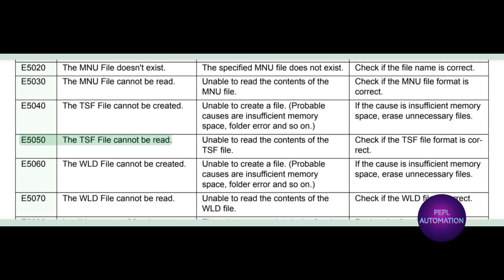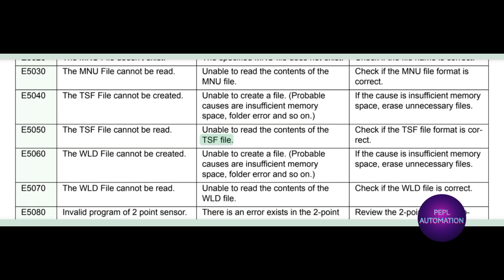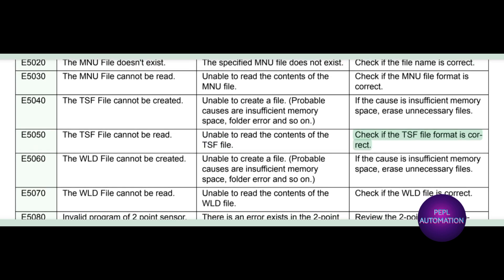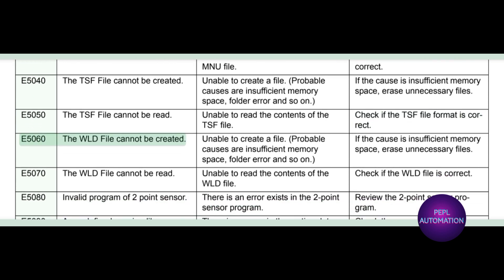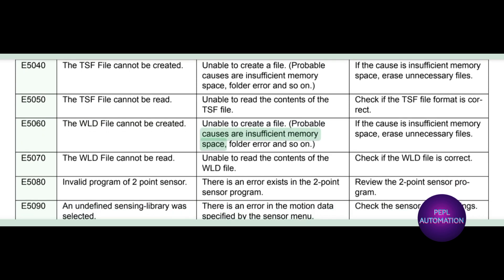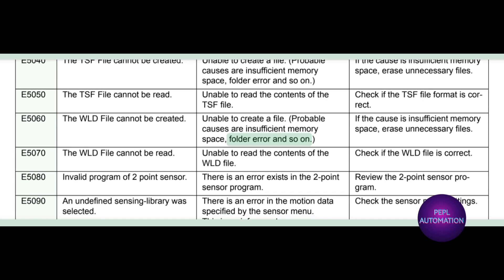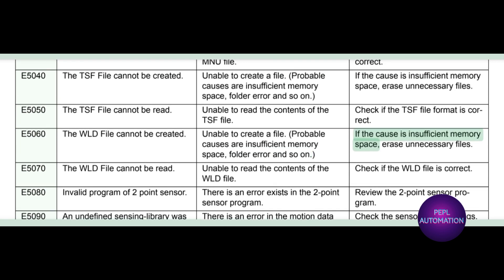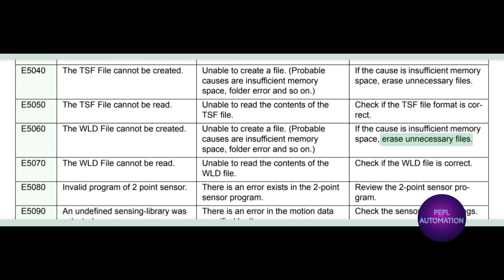E5050: the TSF file cannot be read. Unable to read the contents of the TSF file. Check if the TSF file format is correct. E5060: the WLD file cannot be created. Unable to create a file. Probable causes are insufficient memory space, folder error, and so on. If the cause is insufficient memory space, erase unnecessary files.